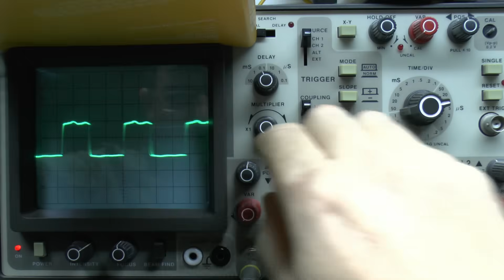Now this is the output we get on the oscilloscope here, and as you can see it's a rather strange waveform. It's sort of roughly a square wave, but seems to be varying in both amplitude and frequency as well. I'll just shade that with the book there, it might be a bit easier to see. Now this device claimed it was an output from 20 kilohertz to around 60, so it seems to be covering a certain range there. Now in terms of settings here, the volts per division we're actually on 20 millivolts per division, so I'll sort of alter that there. At the maximum it's around 2.5 divisions, so it's going to be around 50 millivolts or so, peak to peak there.